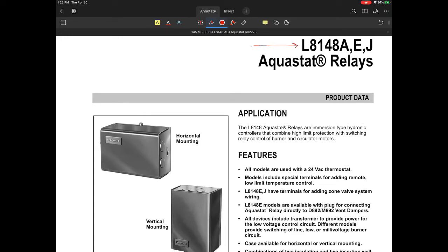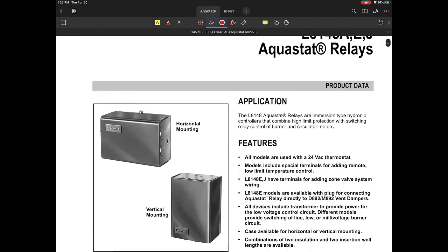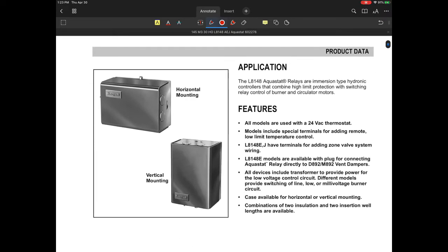This particular Aquastat that we're looking at, what we call an Aquastat relay, is a type that's going to be mounted usually on a boiler system where there would be a well, a temperature well, that creates that isolated barrier between the Aquastat sensing bulb and the fluid from the system. So it makes it easier for changeout. And we'll take a look at that coming up in a little bit.